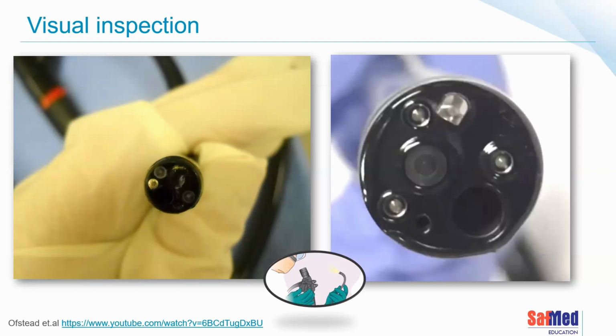So some international guidelines at the moment are calling for inspecting inside the scope using a borescope. There's some controversy around that, because not many people have inspected inside the bores or channels before. So how do we know whether that's just a little scratch or a scratch that needs repair? There still needs to be some guidelines going forward as to what you're seeing with the borescope and when there's something you need to act on. But certainly using borescopes, we've seen all sorts of debris, contaminants, brushes—an amazing amount of things inside the channels of the scopes.